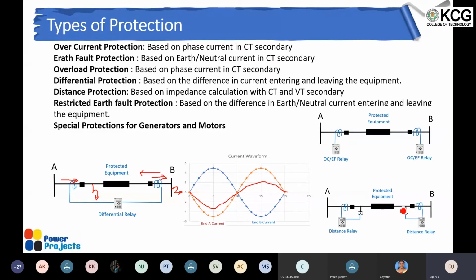And there is another protection we'll talk about, and then we'll go to the communication part. The distance relay protection: basically the distance relay is measuring the impedance, in other words, distance, isn't it? It is mainly used for long transmission lines. If there is a fault somewhere in the system, the impedance ZL that comes here depends on at what percentage of the transmission line the fault has occurred. So based on that, the impedance will be coming.